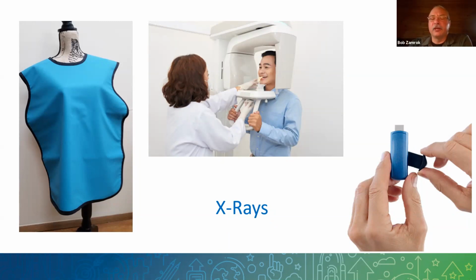From a standpoint of doing installations, what they're going to want to see soon, and Pennsylvania currently does this, is you have to do a radiation survey, and they will not let you install a 3D machine until you submit a survey. So they want to know where the machine's going, how far away the operator is going to stand. It's all based around the radiation safety policies of the office. So that's a written policy you're going to have. This is where the operator has to stand, so that they know where all the measured doses of scatter radiation are, so that you don't go over what the recommendations are for radiation exposure.